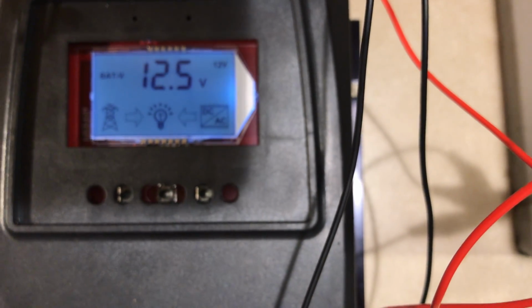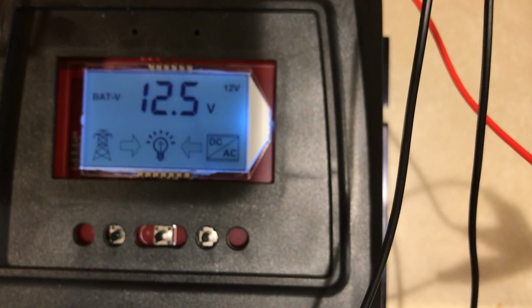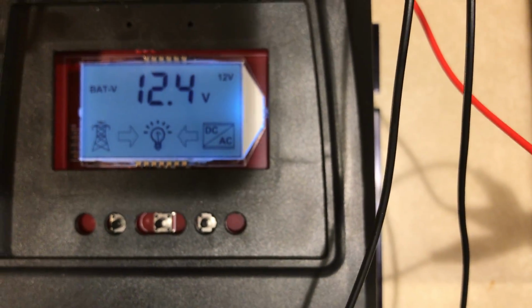Now it's discharging, so it'll drop down to 11 volts for discharge. And that's how you set up an inverter to run off 12 volts - excuse me, not an inverter, but a transfer switch. The remote is just sampling that 12 volts coming off there, that's what that means right there.